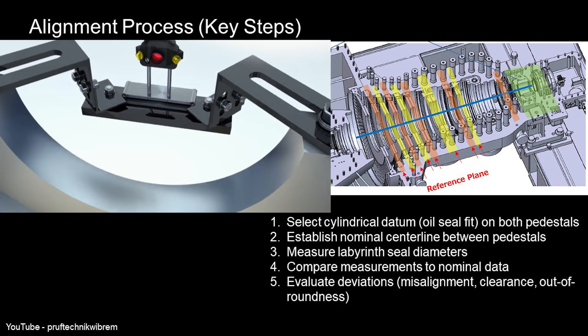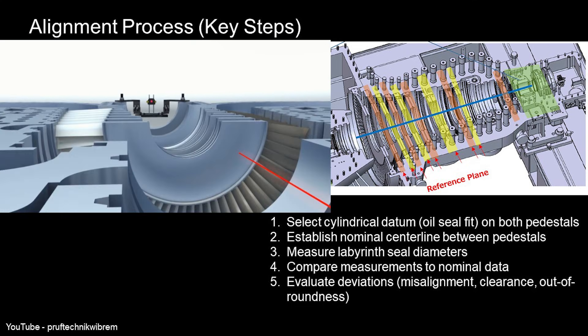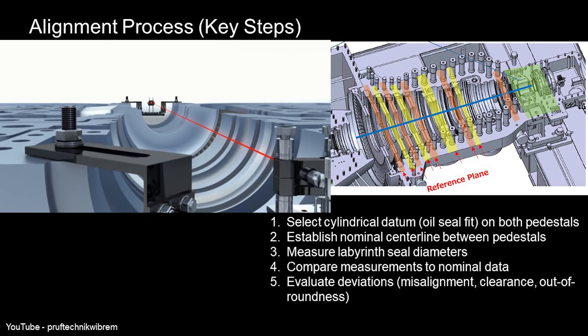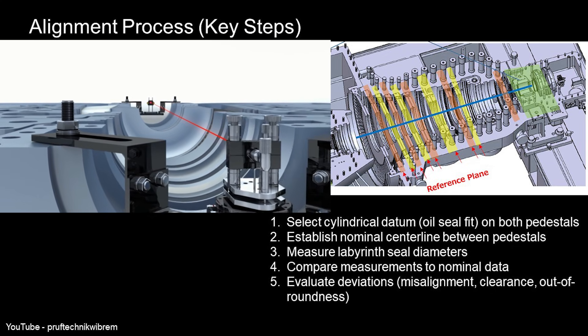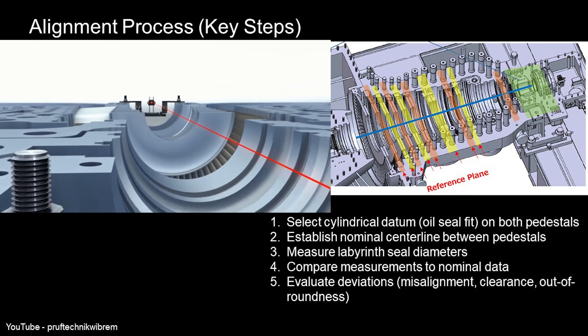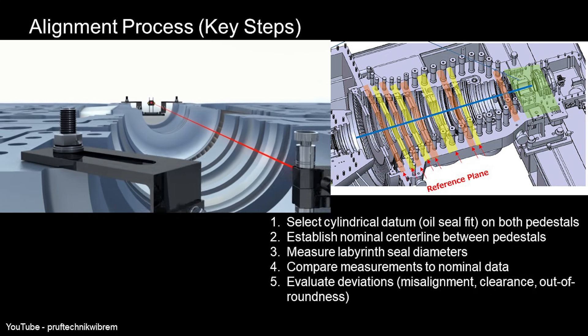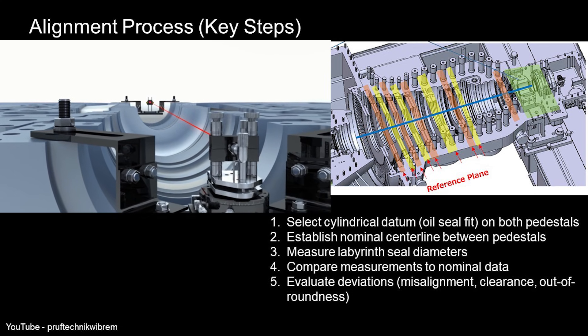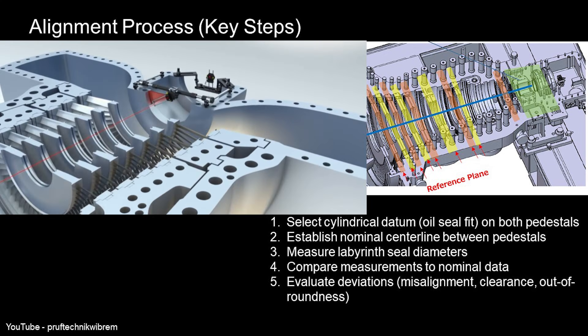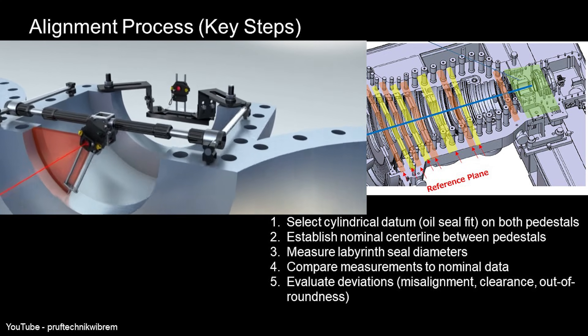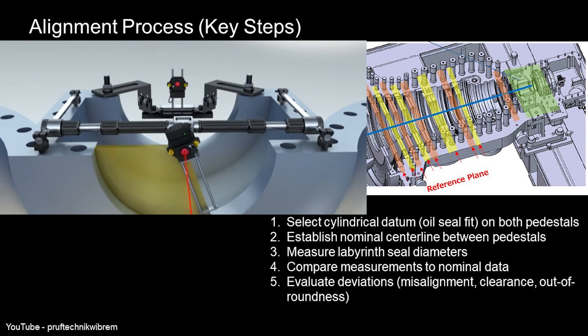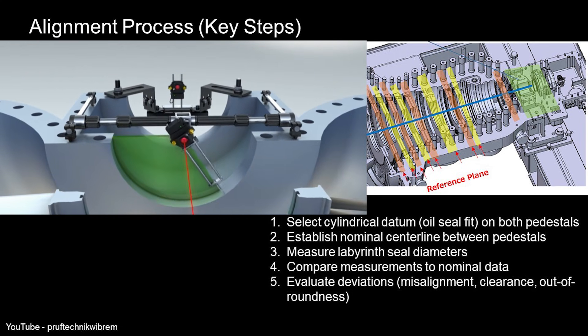First, select a cylindrical reference point — typically the oil seal fit on both pedestals. Then establish a centerline between the two pedestals. Next, measure the seal diameter at each critical point. Then overlay the measured data onto the nominal design specs.